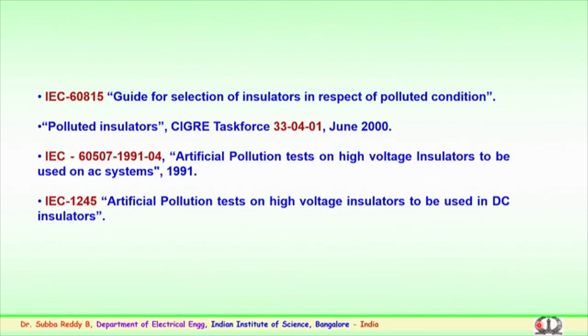60507. This is a technical document which gives the methods of artificial pollution experimentation or tests to be carried out on the various insulators which are to be used in AC transmission systems. There are methods specified for how the insulator is to be contaminated, the spray, and how the experiments have to be conducted. So, for all AC transmission systems, the standards are defined. Similarly, for the DC, IEC 1245 is the standard which gives guidelines to simulate the conditions in the laboratory and how the artificial pollution tests are to be carried out, particularly for DC insulators.